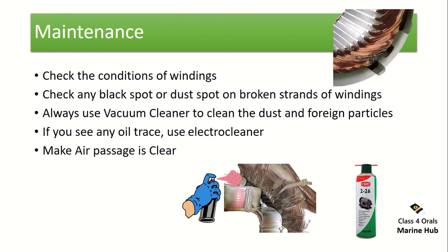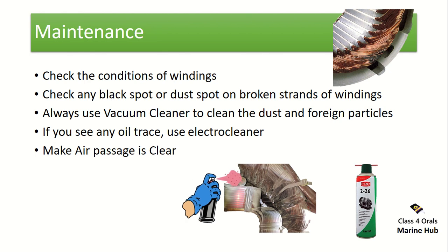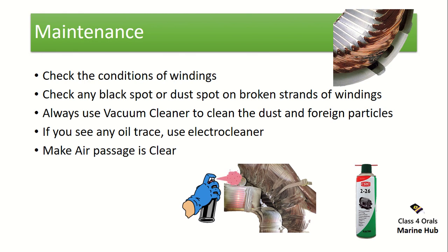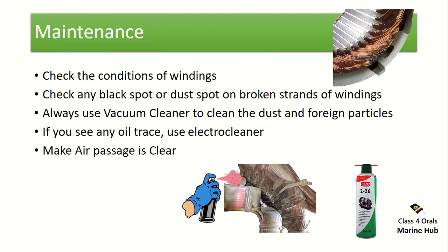Now for the maintenance: the first point is to check the condition of the windings. Check if there are any black spots, dust spots, or broken strands on the winding. If you find any, always prefer the vacuum cleaner to clean the dust and foreign particles, because the vacuum cleaner will absorb all the dust accumulated, whereas a blower will blow the dust all over. You can also use a lint-free cloth to clean the windings.